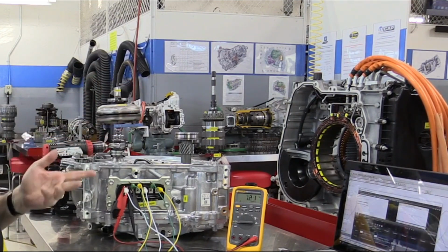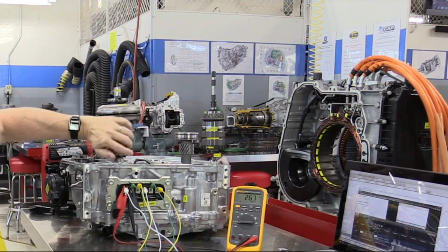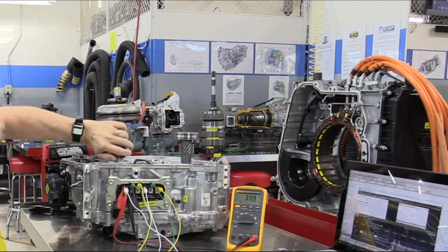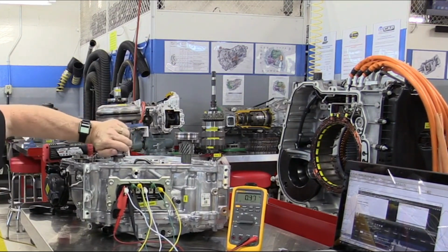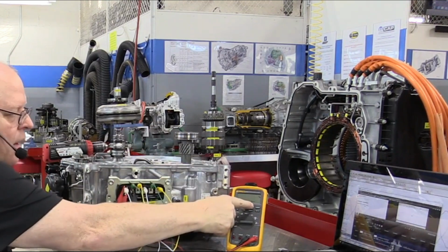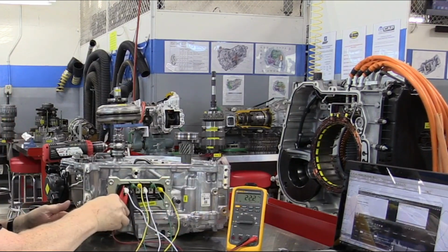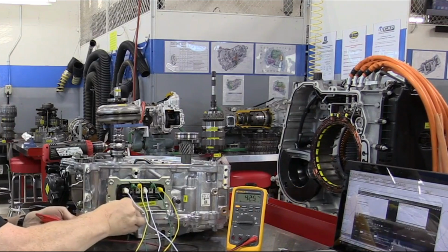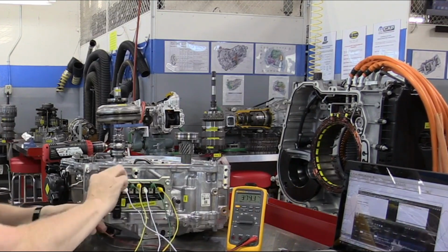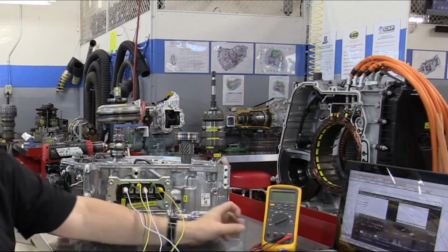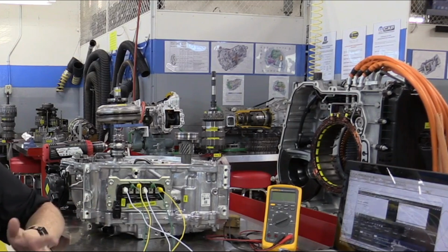If the bearings are stressed beyond their limit, they could fail, causing further mechanical damage to the motor. The loss of magnetic balance might cause the motor to produce abnormal vibration and noise. These mechanical disturbances could lead to loosening of the motor mount or damage to the connected mechanical systems.